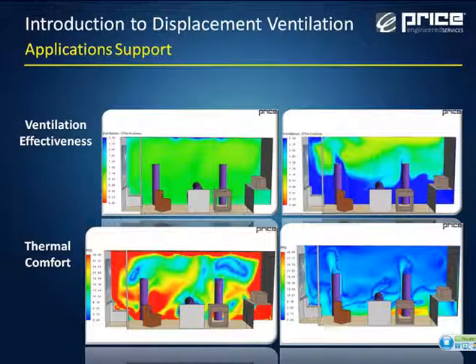If we look at ventilation effectiveness for the displacement case, we see that dark blue area, which is depicting ventilation effectiveness of around 2.25 to 2.5. So it's 2.5 times cleaner than at the return level, which means the contaminants are basically being effectively removed from the occupied zone and not mixed back down. And you can see the flow patterns that the thermal plumes are creating, providing that fresh air zone right around the breathing zone. And the most contaminated area is right at the ceiling, which is exactly what we want, so that whatever each person is breathing out is being carried right to the ceiling and it's not being mixed back down to anyone else in the room.